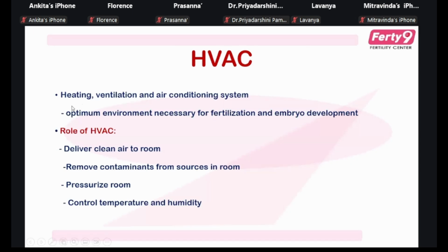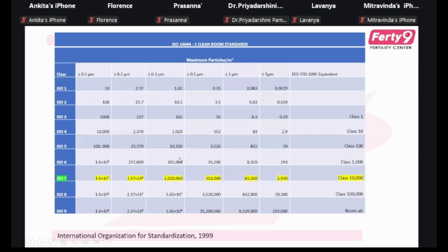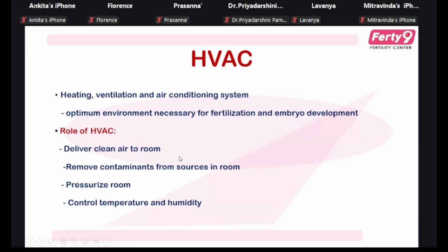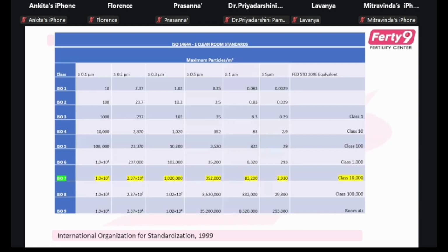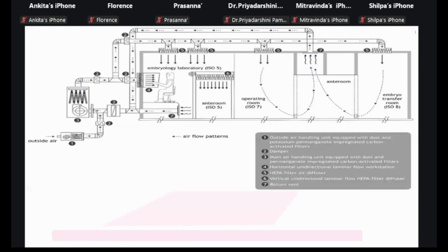Maintaining air quality means the heating, ventilation, and air conditioning (HVAC) system has to be in place for an optimum environment necessary for fertilization and embryo development. The role of HVAC is to deliver clean air to the room, remove contaminants, and maintain pressure, temperature, and humidity. ISO 7 is the standard clean room classification for IVF labs, and particles should be class 10,000, which is very important for a good ART lab.